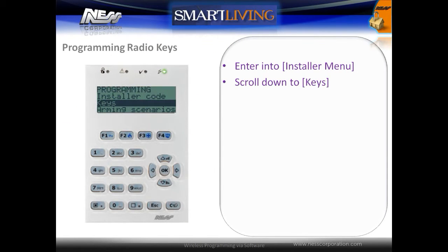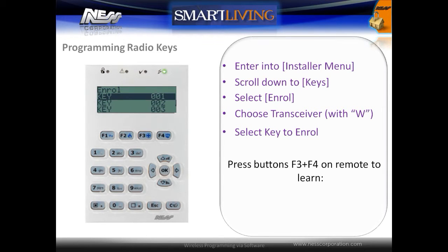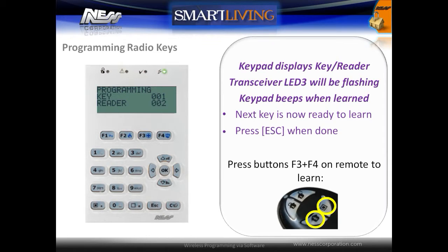To enroll a radio key, enter the installer menu and scroll down to keys. Select the enroll option and then choose the transceiver, which is the reader with a W next to it. Select a radio key to enroll and then on the radio key, press the bottom two buttons, F3 and F4, together. When enrolling, the keypad displays the key and reader currently being enrolled, and the transceiver's LED number 3 will be flashing. Once enrolled, the keypad will beep and progress to the next key automatically. Continue learning additional keys and then press the escape key when done.